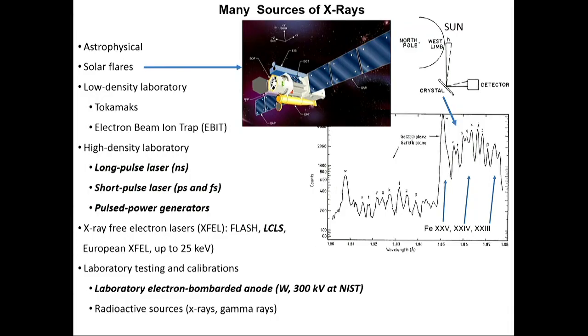Laboratory X-ray sources are typically used for testing your X-ray spectrometer before you take it to one of these large facilities, because you want it to work on the first attempt. Calibrations are also done using laboratory sources. In particular, an electron-bombarded anode: you have a cathode that produces high energy electrons, which are accelerated by a large potential like 300 kilovolts. Those electrons bombard an anode, typically a metal like tungsten, producing energetic photons. There are also very high energy radioactive sources — X-rays and gamma rays.